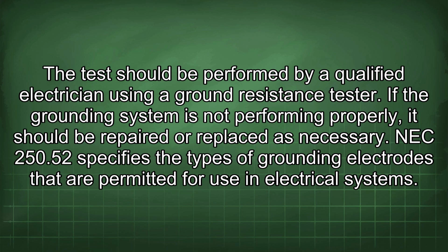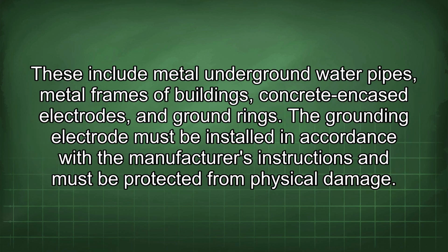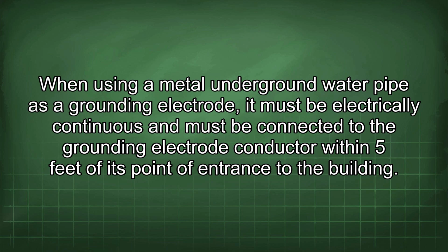NEC 250.52 specifies the types of grounding electrodes that are permitted for use in electrical systems. These include metal underground water pipes, metal frames of buildings, concrete encased electrodes, and ground rings. The grounding electrode must be installed in accordance with the manufacturer's instructions and must be protected from physical damage. When using a metal underground water pipe as a grounding electrode, it must be electrically continuous and must be connected to the grounding electrode conductor within 5 feet of its point of entrance to the building.